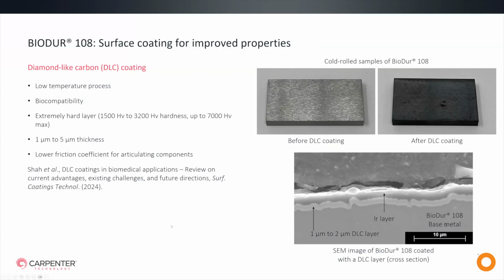In addition to nitriding, BioDur 108 is also compatible with surface coating technologies. So we did confirm in part of the patent that DLC, or the diamond-like coating, is compatible and they do not degrade the matrix. Now the thickness is a little bit thinner, right? But they can provide an extremely hard surface beyond what can even be measured on the Rockwell scale. Again, it can provide some low friction coefficient options, great for articulating components, and the biocompatibility of this particular coating has records and acceptable clinical use. So we have not tested in-depth, in situ, extensive testing on any of these coatings, nor does Carpenter offer these processes, but instead we're trying to show the compatibility of BioDur 108 with processes common to your industry today.